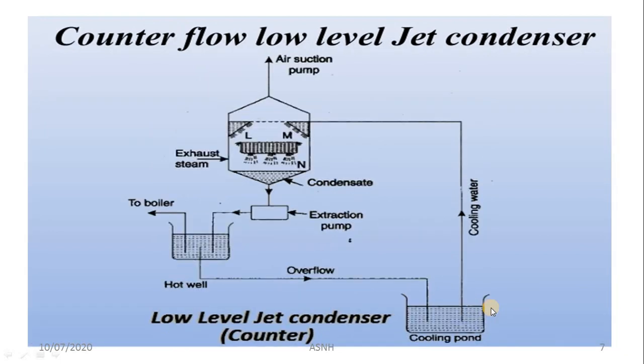Now we will discuss the counter flow condenser. Another name for the counter flow jet condenser is the low level jet condenser, where the condensate extraction pump is mandatory. The name counter flow is given because the direction of the steam entering and the direction of the cooling water entering are totally opposite, in counter direction, and mixing takes place. So it is called a counter flow jet condenser.